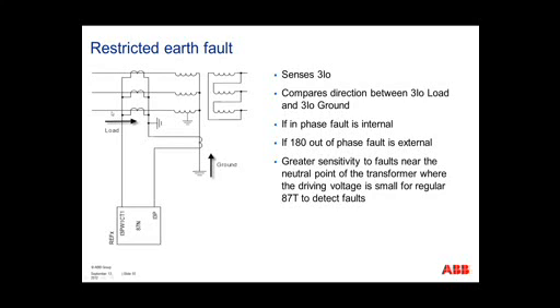If you have a phase to ground fault outside this transformer, say a grounding point here, you would have zero sequence currents leaving the transformer through the neutral leg, going through the transformer and out to the system. This relay will measure the zero sequence currents coming out of the transformer and calculate the zero sequence currents leaving the transformer. It will perform a differential, see a net zero sequence current of zero, and restrain from tripping. However, if you have a fault inside the transformer very close to the neutral, you will see zero sequence currents coming from the transmission side, plus zero sequence currents coming through the neutral of the transformer, showing a net zero sequence current that the relay sees and operates on.